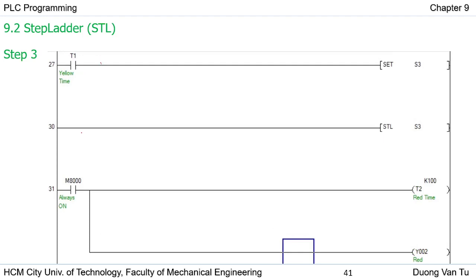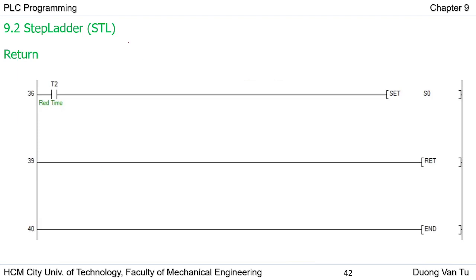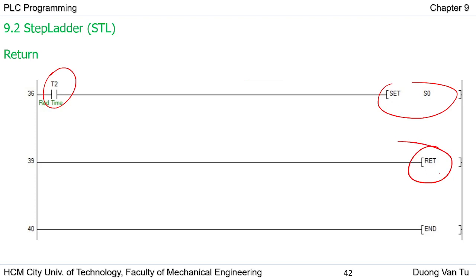For step three, I put one network as the action. Finally, we use the condition to SET step zero and use the RETURN instruction. Even if you SET step zero, without the RETURN instruction the ladder diagram will produce an error, so we must use the RETURN instruction. This is the content of this chapter. I hope you understand. If you have any questions, we will discuss them in class.